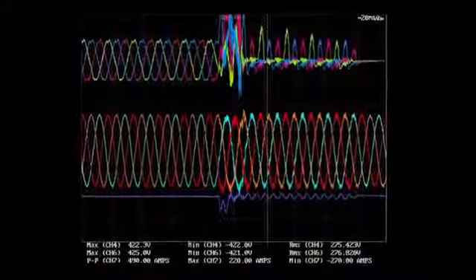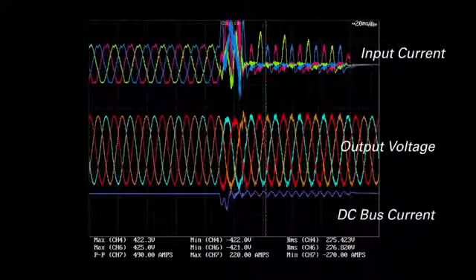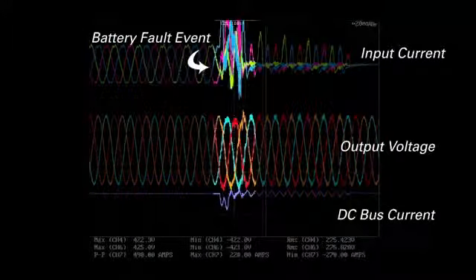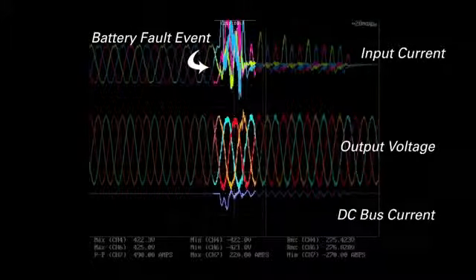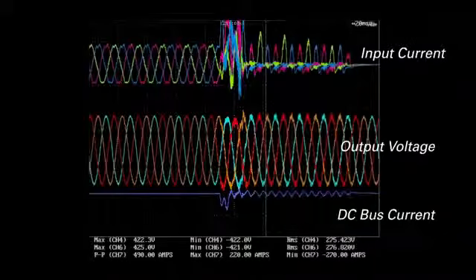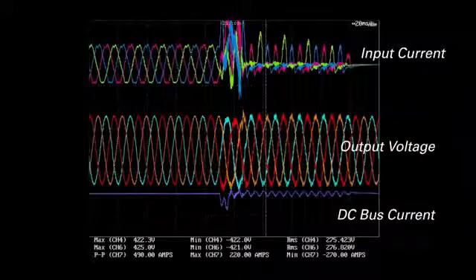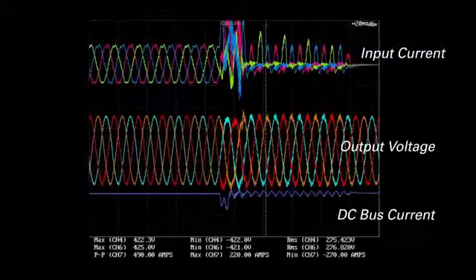The images displayed here show the fault that we just applied to the unit. They represent the battery plus to ground condition. They demonstrate the robustness of the 9395 product. The unit emergency transferred to bypass and maintained the critical load.